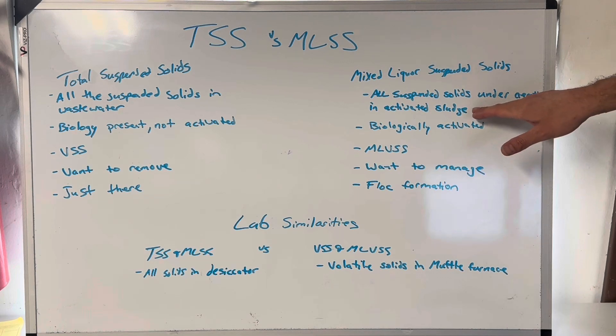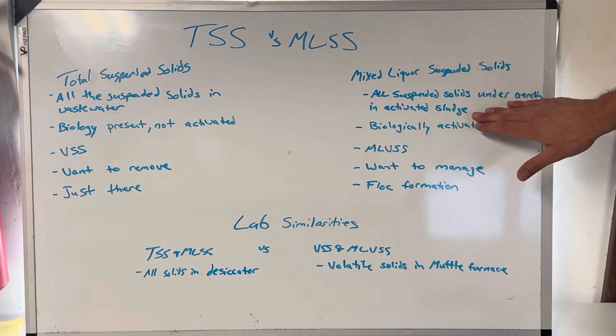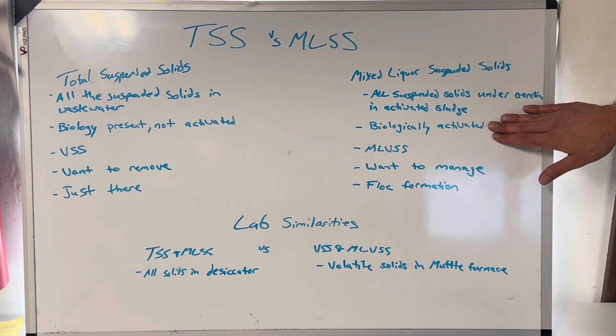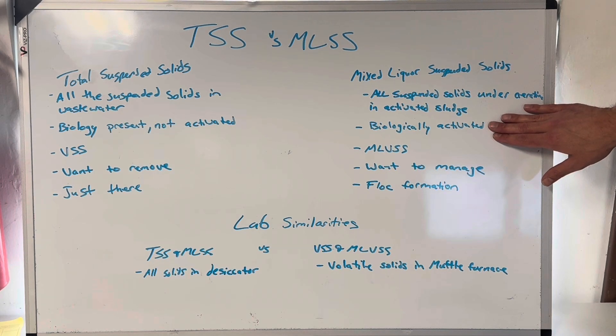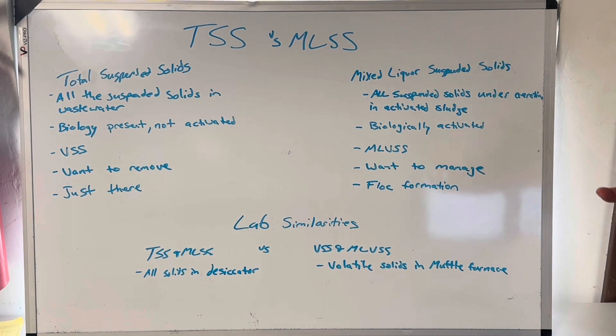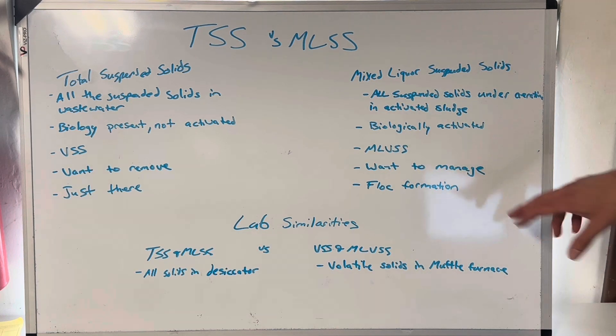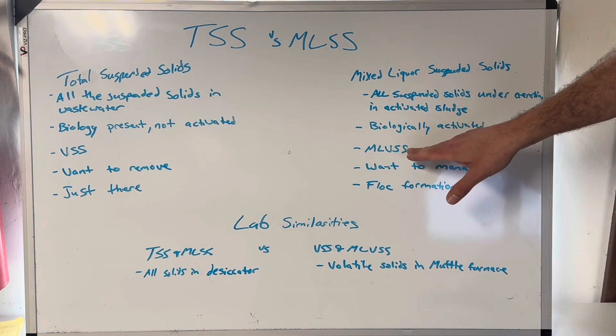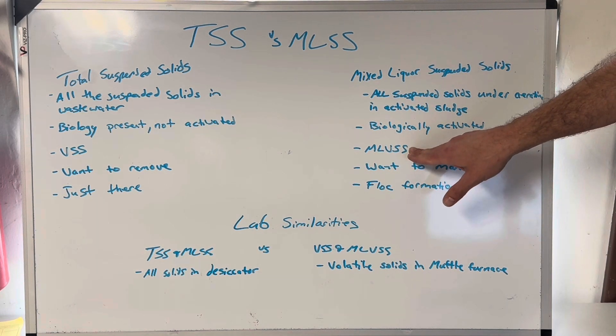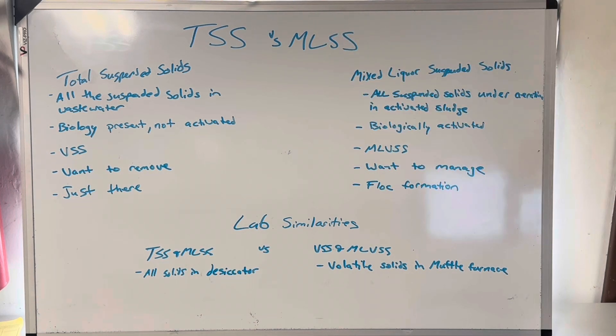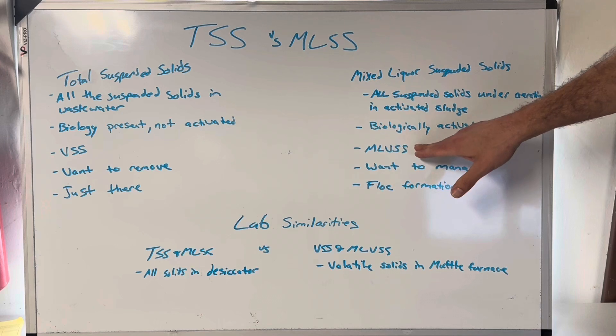For the advanced folks, yes, you can go through an anoxic, aerobic, and anaerobic zone, but let's keep this simple for right now. MLSS is biologically activated. You put this stuff under a microscope and you can see it's teeming with biology — by design. We are using aeration strategies to create certain environments that attract a certain biology that consumes the wastewater. MLSS is comprised mostly of MLVSS — the mixed liquor volatile suspended solids — this is the stuff that eats the waste. The VSS food goes in and the MLVSS consumes it.